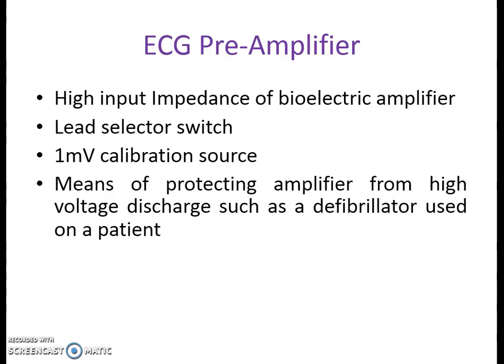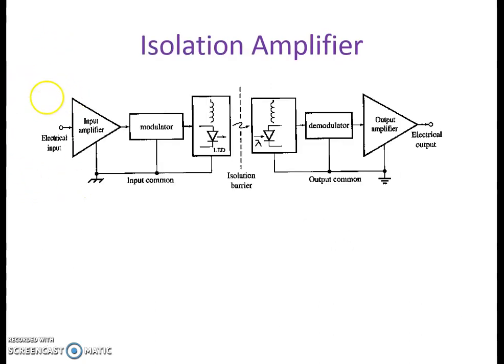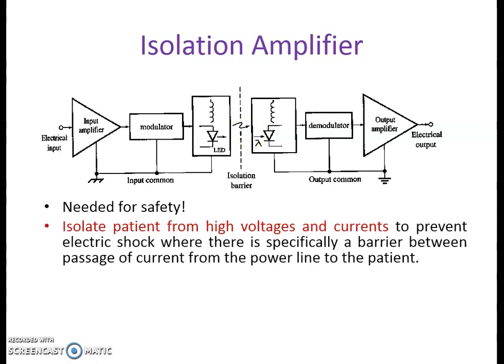The preamplifier should have a means of protecting the amplifier from high voltage discharges such as from a defibrillator used on the patient. Sometimes the preamplifier will also have an isolation amplifier. In the isolation amplifier, on one side we have electrical input and on the other side we have electrical output. Both sides — input and output — are isolated from each other by means of an optical arrangement. This arrangement is specifically needed for safety. It isolates the patients from high voltages and currents in order to prevent electrical shock, creating a barrier between the passage of current from the power line to the patient.